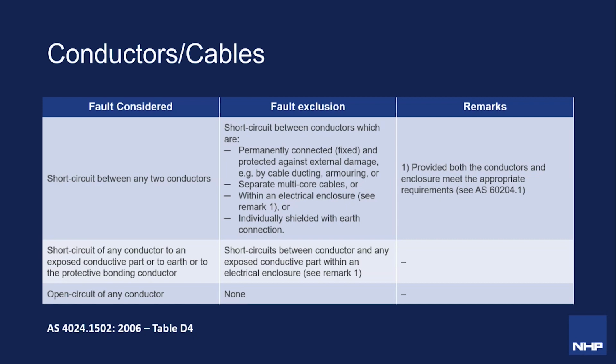However, some faults cannot be excluded. The open circuit of any conductor has no rationale for excluding this fault. Therefore, this is a fault that we must consider and monitor with the diagnostic capabilities of our safety control circuit.